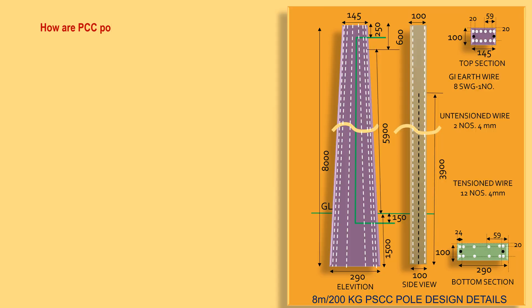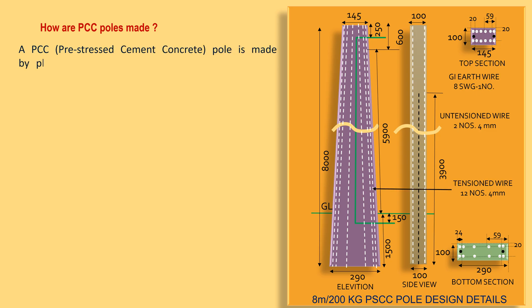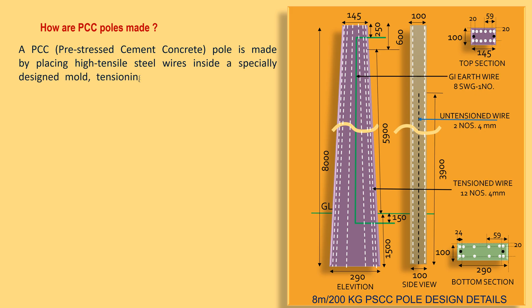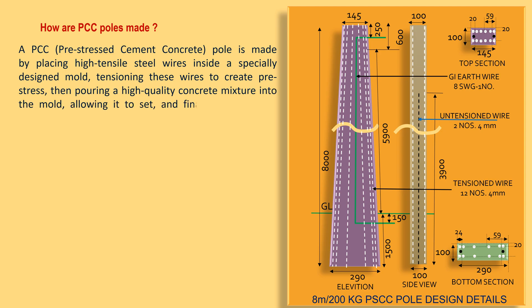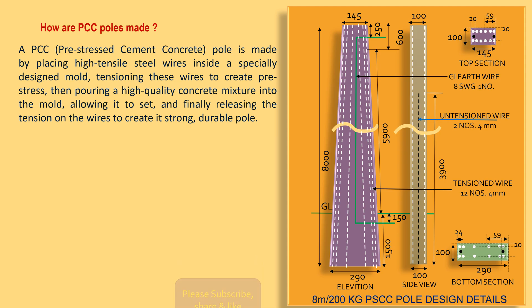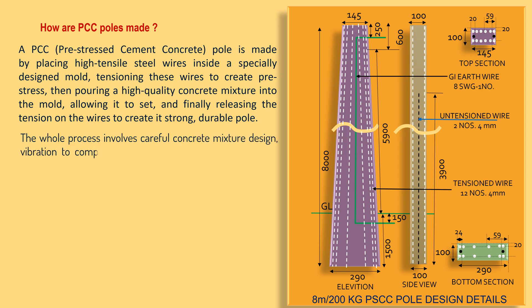A PCC pole is made by placing high tensile steel wires inside a specially designed mould, tensioning these wires to create pre-stress, then pouring a high quality concrete mixture into the mould, allowing it to set, and finally releasing the tension on the wires to make it stronger. The whole process involves careful concrete mixture design, vibration to compact the concrete, and a curing period to achieve the desired strength.